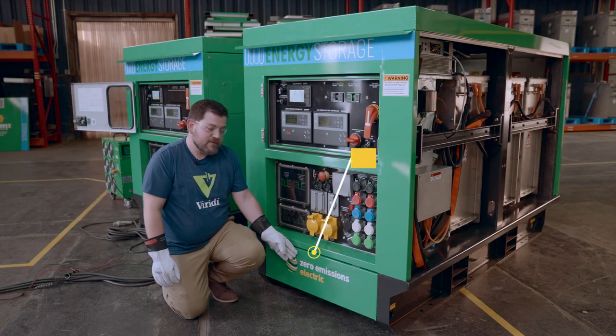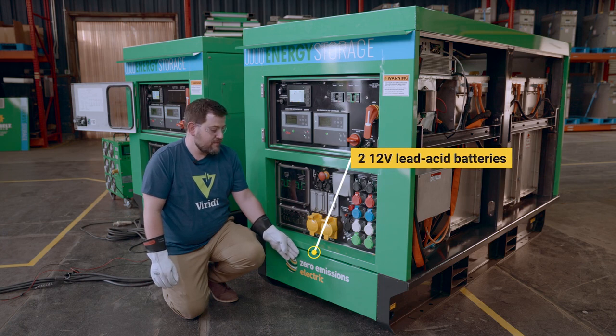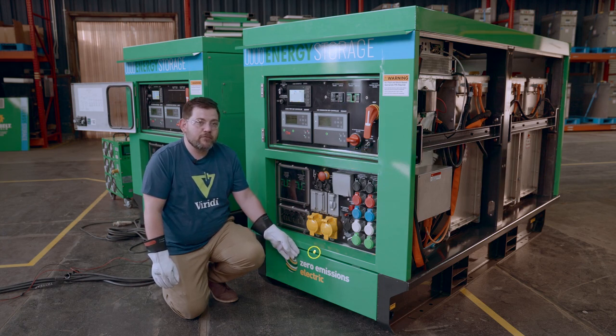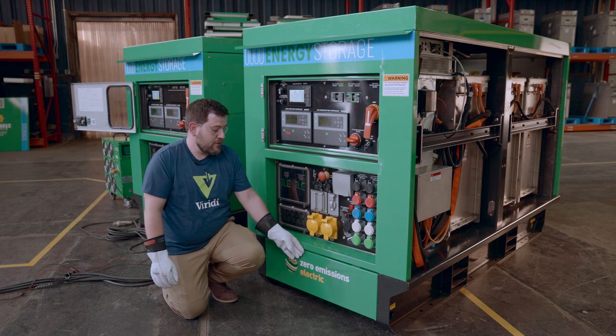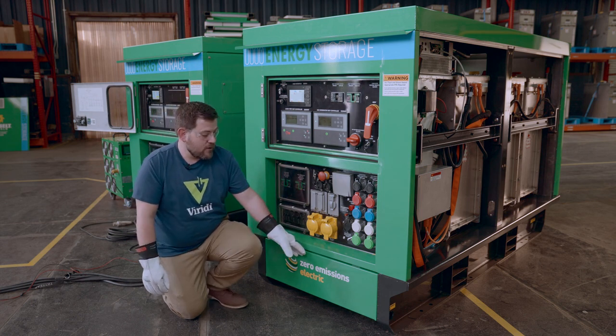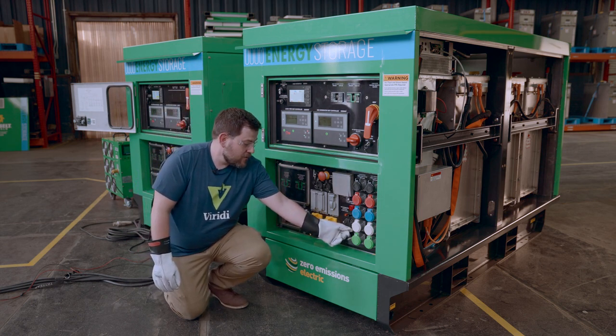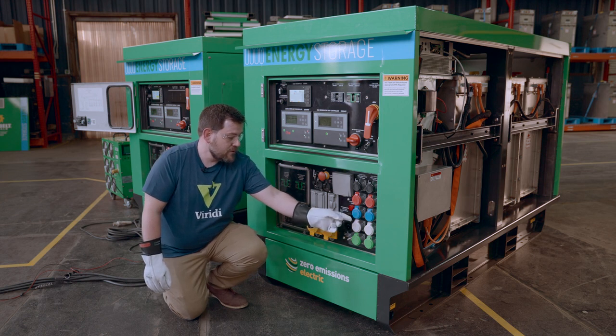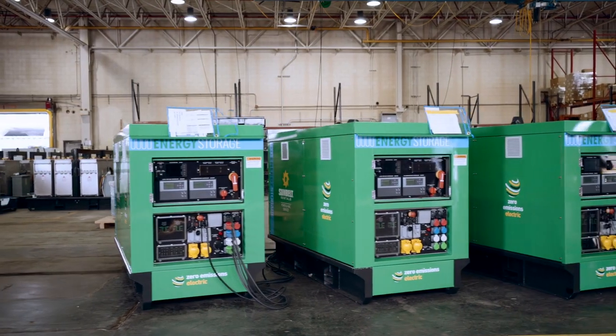Behind this lower panel are two 12 volt lead acid batteries in series, which provide our 24 volt power to power up the unit. If one of those are low or both are low, we also have a Norco trickle charger that you can plug into a normal 120 volt outlet to recharge those batteries.